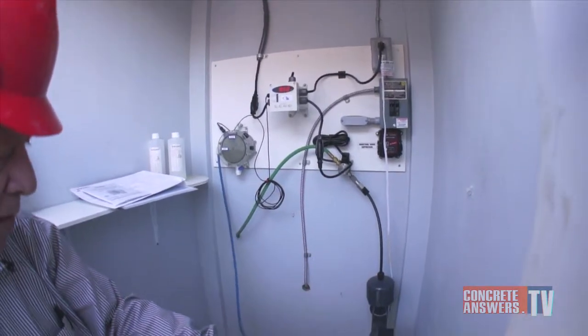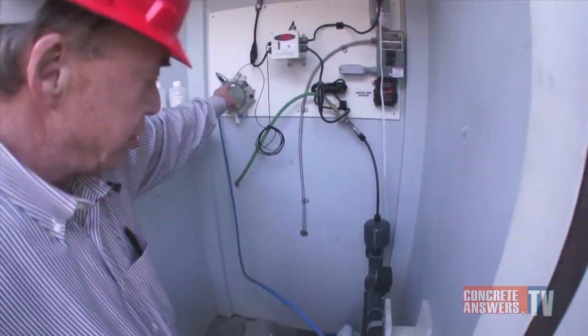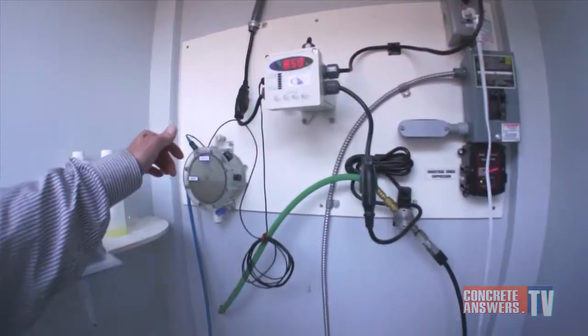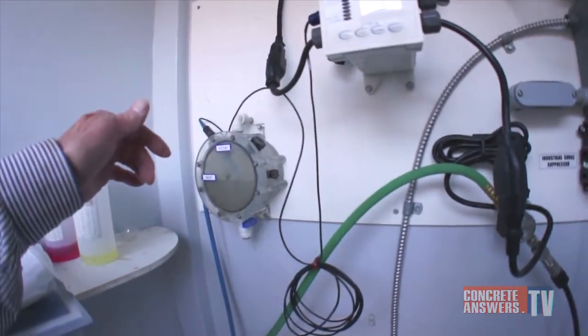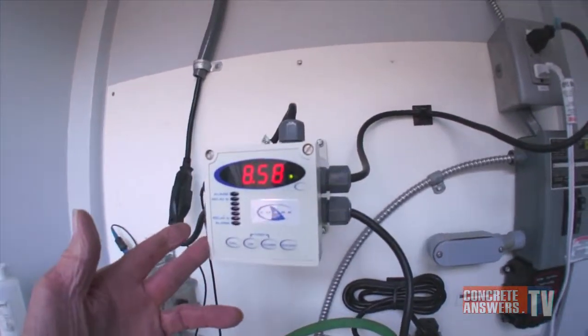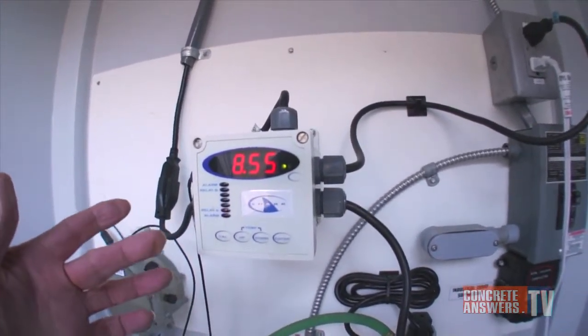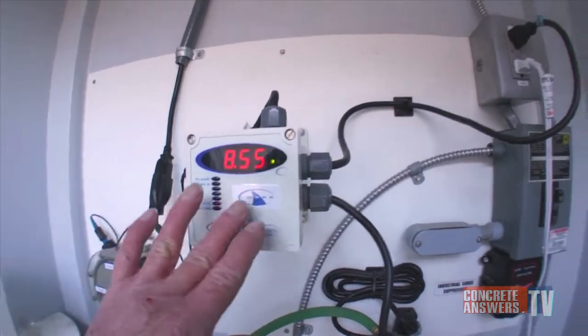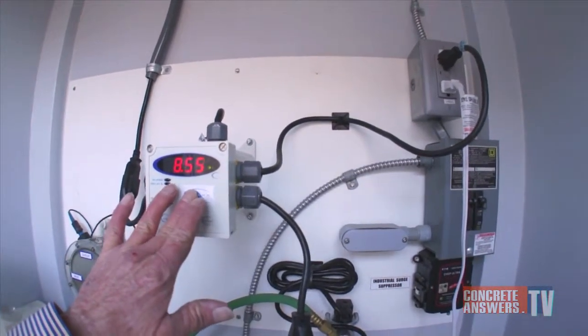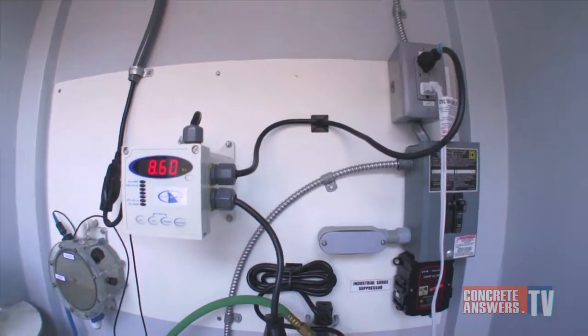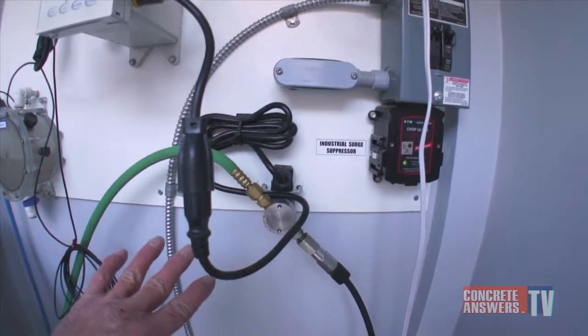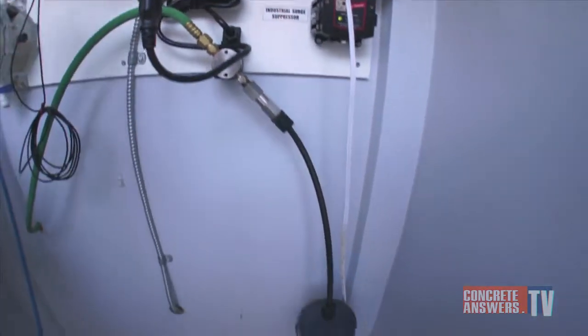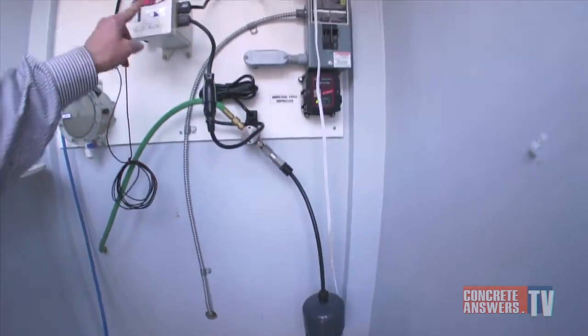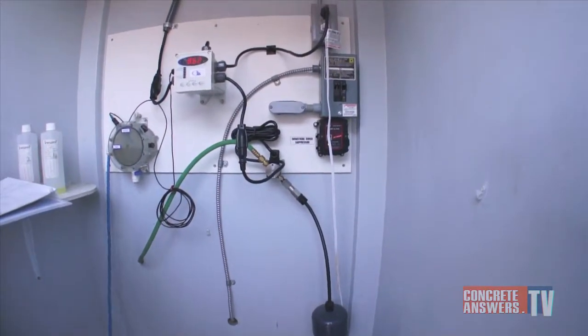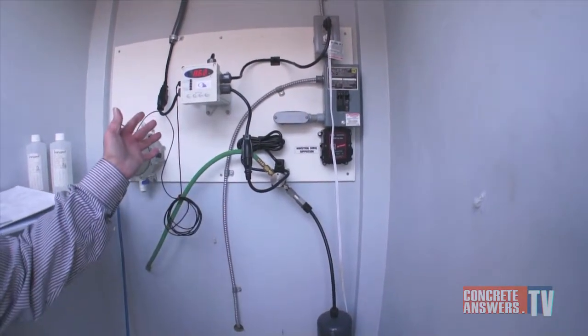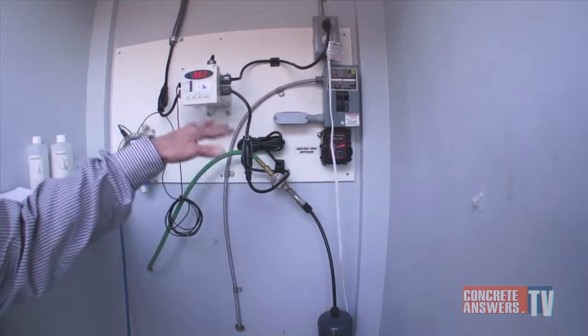We pull a sample from the operating loop through our sample cell. The pH probe reads the pH of the water and reports to a PLC or controller here. If the pH is over 8.25, this PLC will turn on relay A, which I believe you just heard it pop on, and it will feed CO2 until the pH reaches 7.25, at which point it will just pump water until the pH of the basin exceeds 8.25 again. It'll come back on and knock it back down.